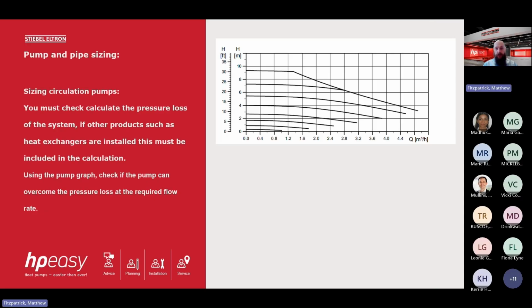So just a small section on sizing circulation pumps. So you must always check the pressure loss of the system. If you have additional elbows and bends in the heating system and the primary system from the air source or ground source heat pump to the cylinders, this will increase the pressure. The pump has to work harder to send the energy around the circuit. But there's also other aspects as well. Heat exchangers. So the heat exchanger inside the air source or ground source heat pump will have a pressure loss because it's a smaller diameter and the pump has to work harder to get it through this component. Any external heat exchangers will have a temperature loss and a pressure loss as well. So these need to be factored in.